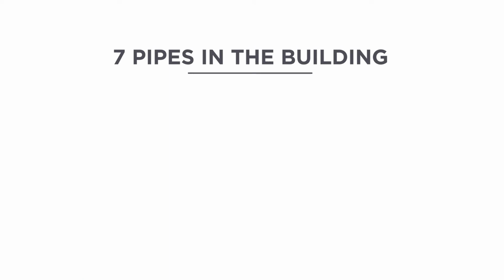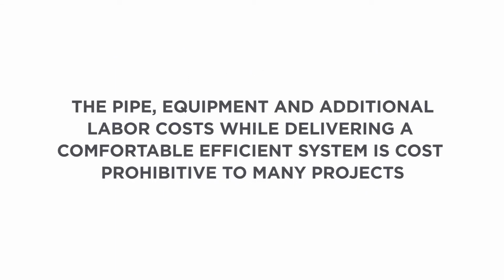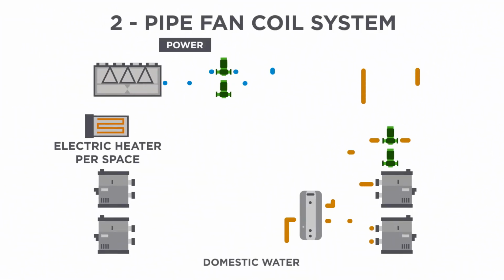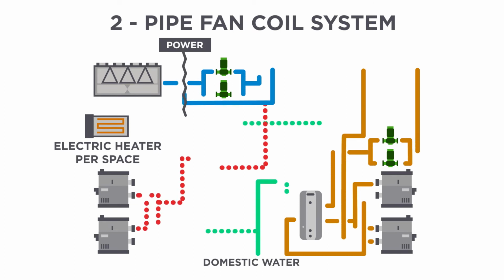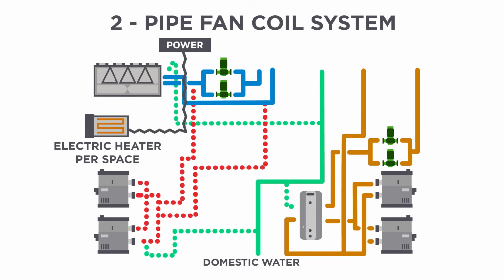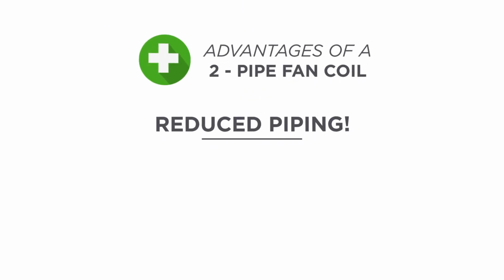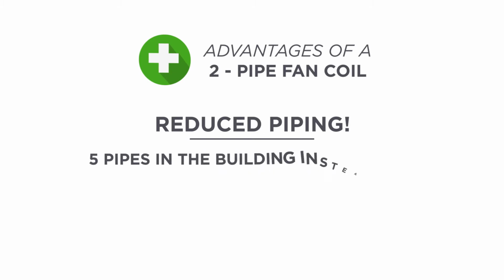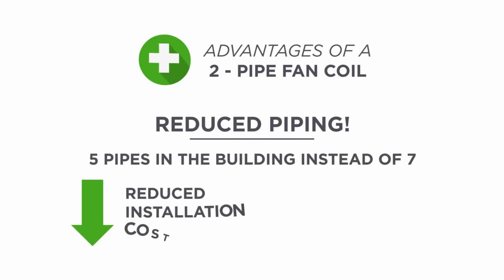This system requires 7 pipes in the building, not counting sanitary drains, 4 for the heating and cooling, and 3 for the domestic water system. The pipe, equipment, and additional labor costs while delivering a comfortable, efficient system is cost prohibitive to many projects. The next system of choice, typically, is the 2-pipe fan coil system. The advantage here versus the 4-pipe hydronic system is that with reduced piping, the building will now have 5 pipes in the building, not including sanitary, instead of 7, which translates to reduced installation cost.